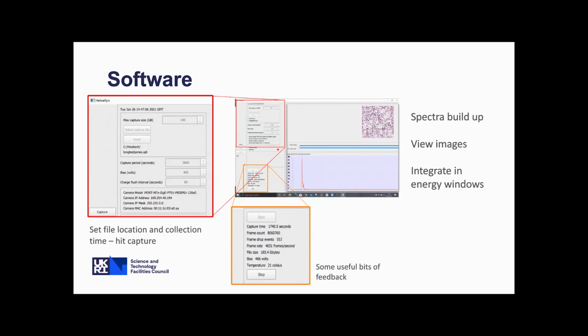And then the images that you can see is that you've got a spectrum. So that raw data has been converted into an energy spectrum per pixel and a total spectrum from all the pixels. And then you've got some sliders here, which allow you to define an energy window, which means then you get an image for a particular energy range of interest. So it's a very simple and user-friendly software that you can get to grips with quite easily.